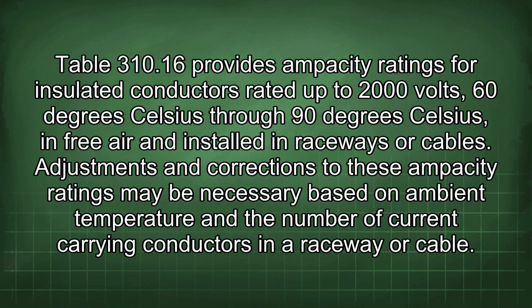Table 310.16 provides ampacity ratings for insulated conductors rated up to 2000 volts, 60 degrees Celsius through 90 degrees Celsius, in free air and installed in raceways or cables. Adjustments and corrections to these ampacity ratings may be necessary based on ambient temperature and the number of current carrying conductors in a raceway or cable.